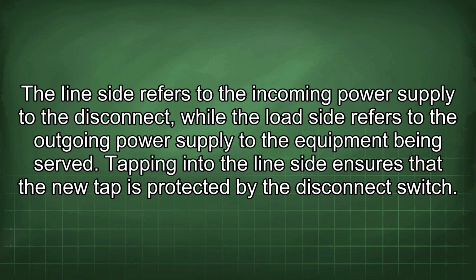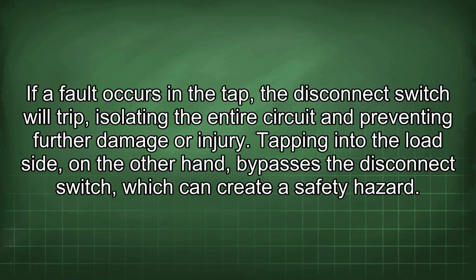Tapping into the line side ensures that the new tap is protected by the disconnect switch. If a fault occurs in the tap, the disconnect switch will trip, isolating the entire circuit and preventing further damage or injury. Tapping into the load side, on the other hand, bypasses the disconnect switch, which can create a safety hazard.